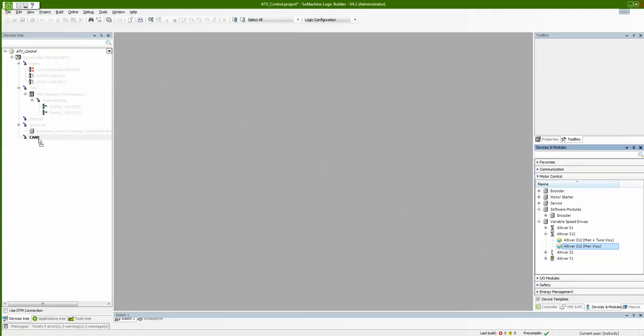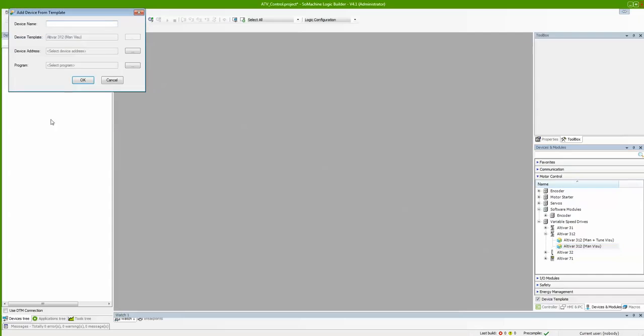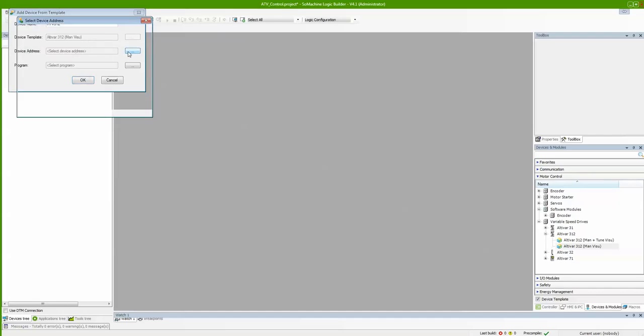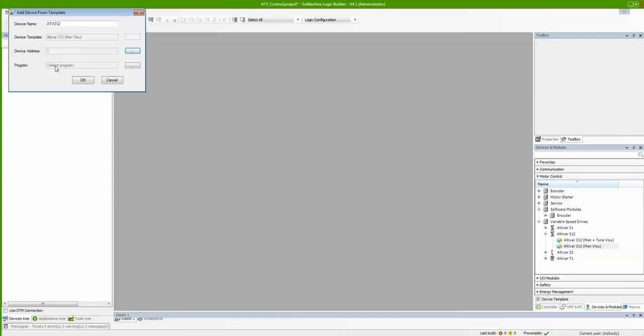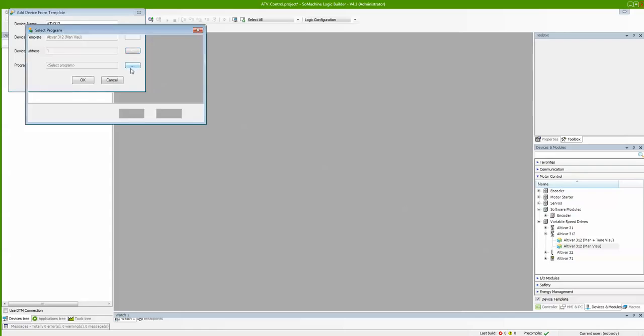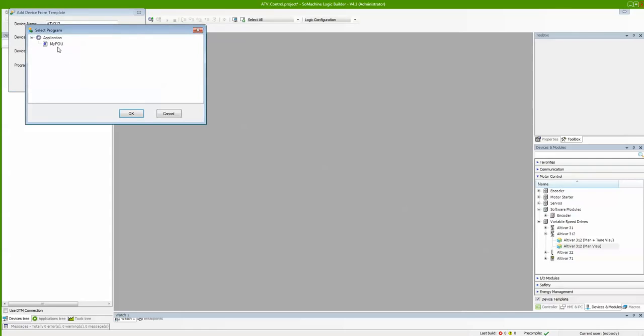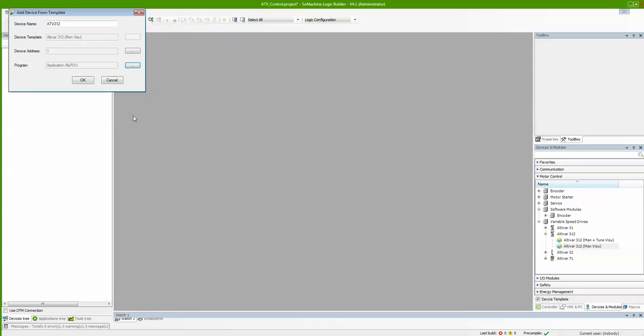The only place I can drop it is my CANOPEN — other places are grayed out. I drop it, call the device name 'ATV312'. This will be my axis reference, which I'll use later as input to my function block. My CANOPEN address is one on this device. The program section where my function block will be added is my one and only POU. I confirm.